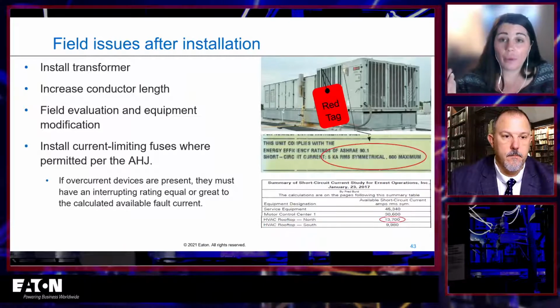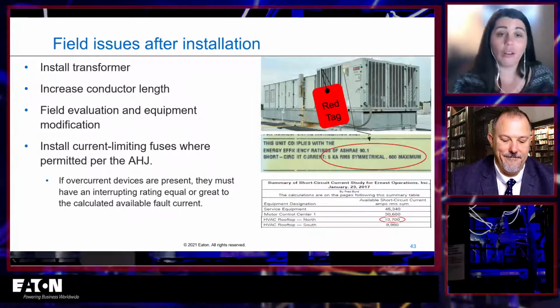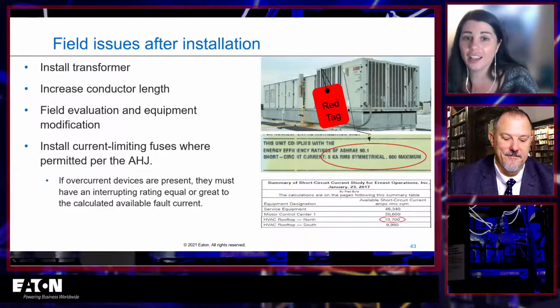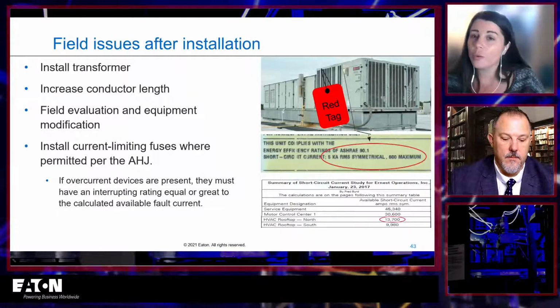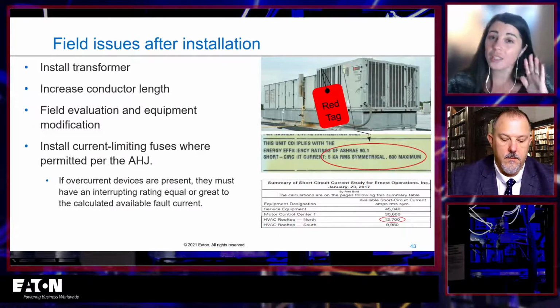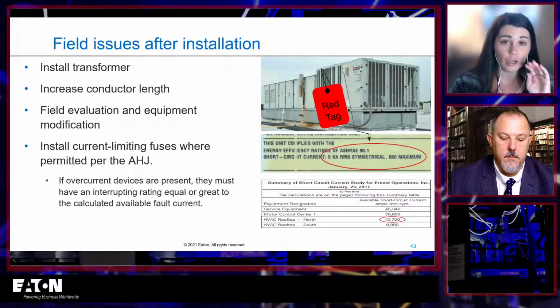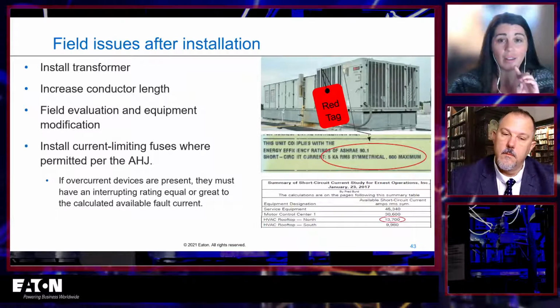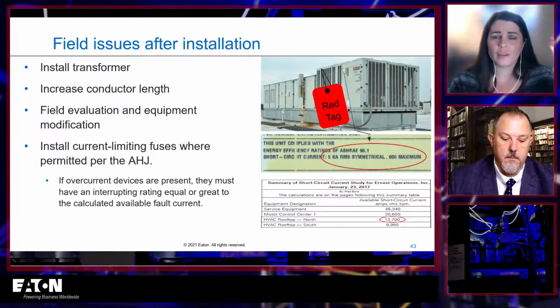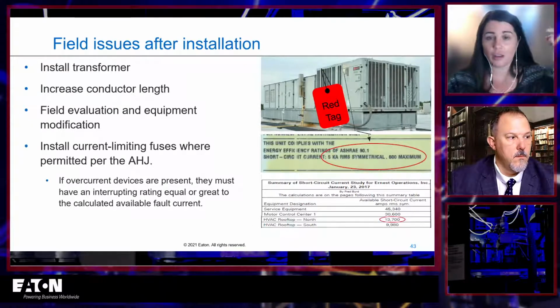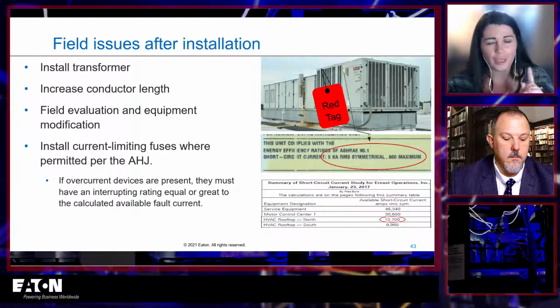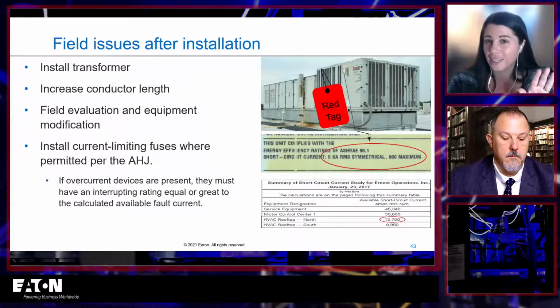And then the last one, this is the one why people call me all of the time, right, is: can I install a current limiting fuse? And it's really important to note that for most pieces of equipment, there's two ways we can do this. But for most pieces of equipment, when we install a current limiting fuse in front of it, we are installing the current limiting fuse in order to increase its short circuit current rating, not to reduce the available fault current. Right? A lot of people say, oh, it's a current limiting fuse. You put that in front of it, it limits the current to this, and that's less than the rating, and it's all okay. That's not actually the logic we get to use for control panels.